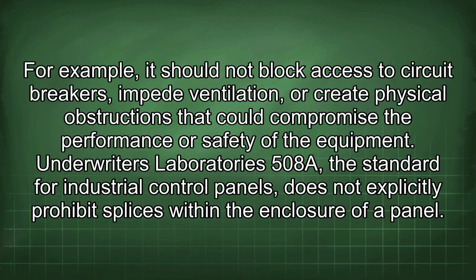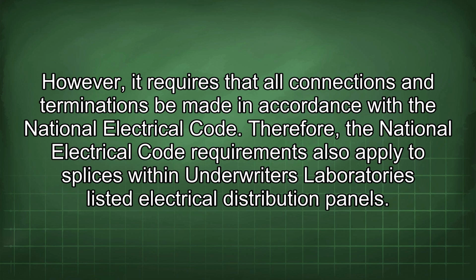Underwriters Laboratories 508A, the standard for industrial control panels, does not explicitly prohibit splices within the enclosure of a panel. However, it requires that all connections and terminations be made in accordance with the National Electrical Code. Therefore, the National Electrical Code requirements also apply to splices within Underwriters Laboratories listed electrical distribution panels.